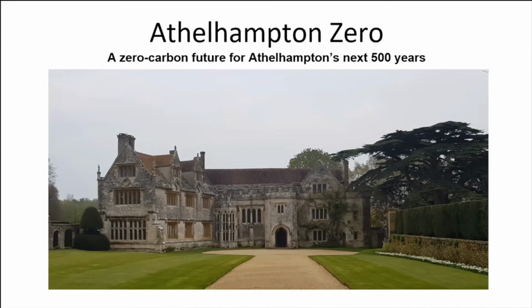I personally thought they were a little bit over the top in terms of the heat loss that they said we ought to allow for. As a result, wherever we could, we followed what they said in terms of putting in either slightly bigger radiators or underfloor heating, maybe combining that with a radiator, whatever. But where that just wasn't going to work, where they were saying, oh, you've got to put a great big new radiator in, completely covering up this historic whatever, then I just gently said no.